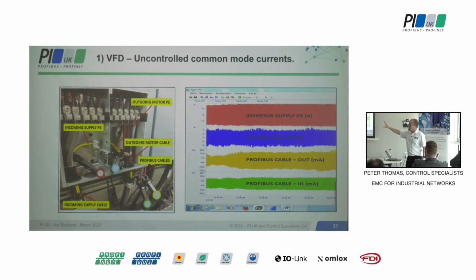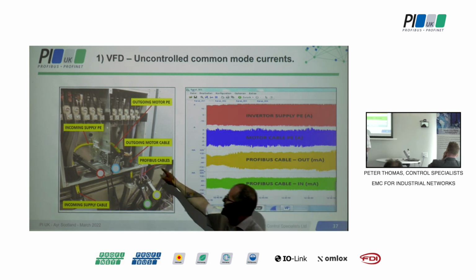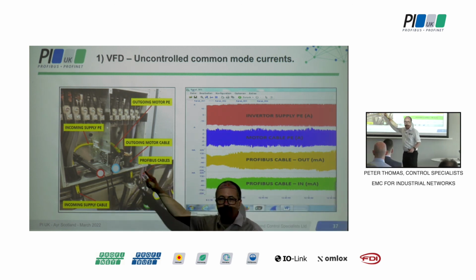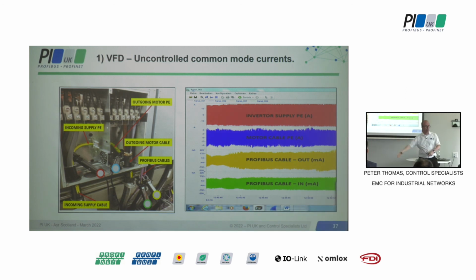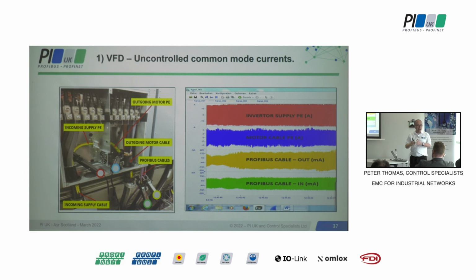But this is now, that current is not flowing out of the drive. What is happening is you've got capacitive coupling from the motor cable getting into the bonding infrastructure, because these guys have twisted the shield. That's a high impedance. It's gone into the bonding infrastructure and now it's coming back into here. Now, that is megahertz, not 50 hertz. Think of your accidental antennas.